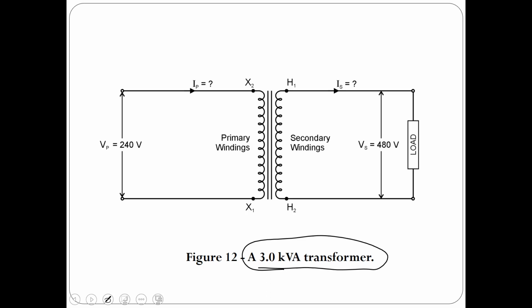So right now the primary voltage, we're using it as it's drawn, as a step up here. The X winding has a 240 volt rating and 3 kVA, so we could calculate the rating of the primary here if we wanted. That would be 3000 VA divided by 240, which gives us 12.5. The rating of the secondary, 3000 VA divided by 480, is 6.25. So that's its normal input current on the primary, and its normal current on its secondary.